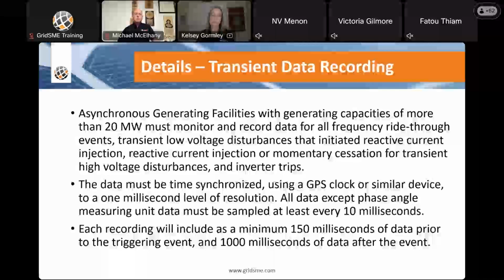So one of the things that I think Mike will dive into a little bit is the difference between the different time sequencing capabilities. So there's precision time protocol and there's NTP. Both of those are options. However, NTP typically is not fast enough to be able to meet this requirement in our experience. So there are a lot of other options being explored by the different inverter manufacturers. IRIG-B is another option that has been put forth by a few of them. But this is really the main crux of where we run into issues with compliance on Appendix H: can all of these devices at both the plant level and the inverter level meet this requirement? So I'll let Mike speak to that a little bit more.